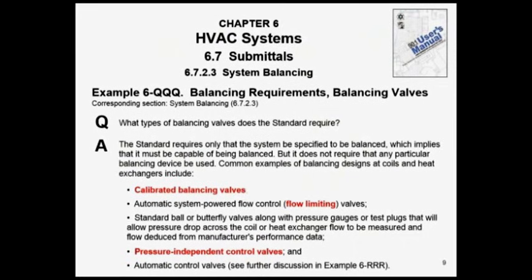So I got to asking myself, looking at this, what does 90.1 say about what we use to balance with? That's kind of a basic question. So I went to the user's manual. Here are some actual questions and answers right out of the 90.1 2010 user's manual on balance. The question to ASHRAE was, what types of balancing valves does the standard require? Bottom line is the standard doesn't specify to the engineer what he uses to balance. It just says you must balance, you must proportion balance, you must have a report. But here are some typical products or items you can use to balance with.